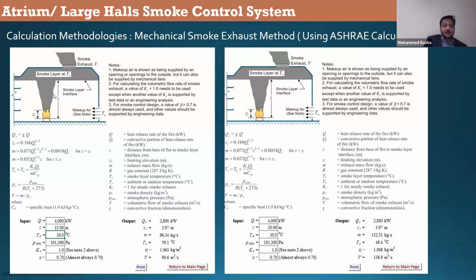Now, for the same atrium, I want to keep a different height. I use the same parameters, whereas I use 20 as my clear height. Look at the fan capacity now: 138.9 meter cube per second, because the fan needs to work more to extract more so that it can maintain 20 meters clear rather than 15 meters. The mass generated here will be 152.51 kilogram per second because of the smoke layer depth. If you change the Z value here, the flow rate required for the fan will vary, so we must be careful about selecting the Z value.